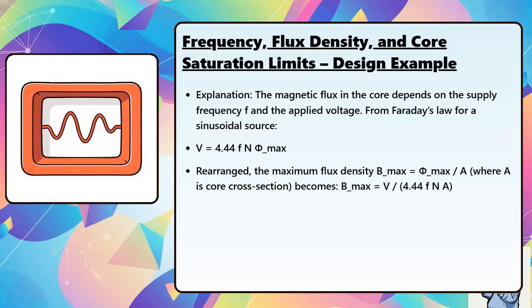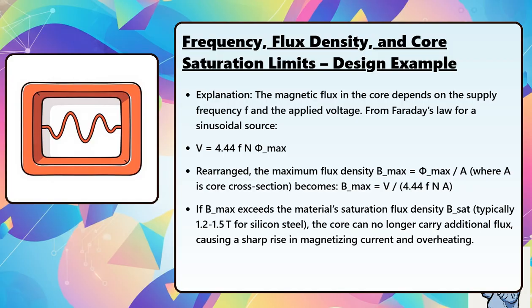Rearranged, the maximum flux density B max equals phi max divided by A, where A is the core cross-section, becomes B max equals V divided by (4.44 times F times N times A). If B max exceeds the material's saturation flux density B sat, typically 1.2 to 1.5 Tesla for silicon steel, the core can no longer carry additional flux, causing a sharp rise in magnetizing current and overheating.